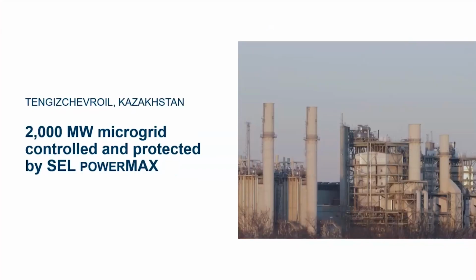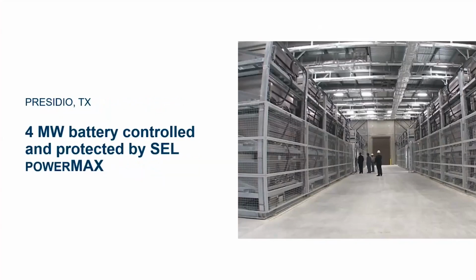Good friends of mine at Chevron, at the Tengiz Chevron facility, this is the single largest oil and gas project in the world, again in contentious ground, with a very austere environment, and they require the ultimate in reliability. And so for this very large gas oil reinjection facility, they have selected an SEL PowerMax dispatch, controls, load shedding, and microgrid control system. This is a project you can look up.